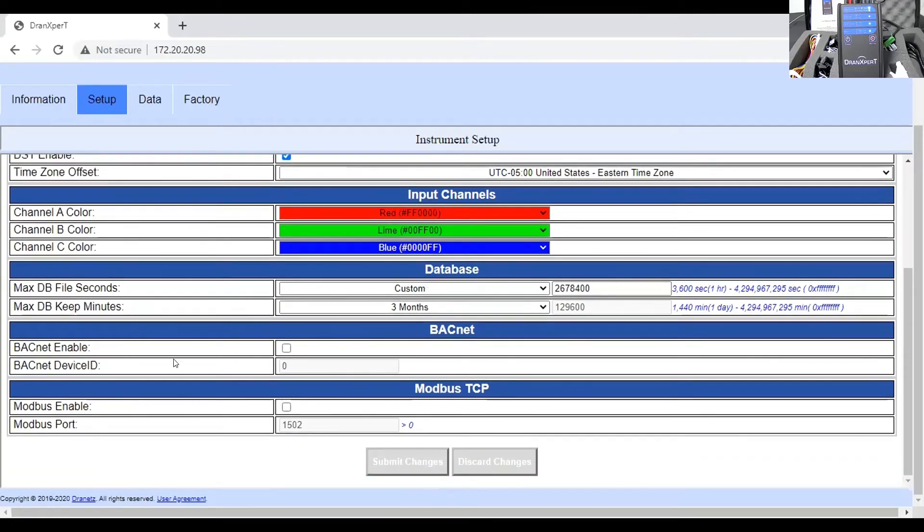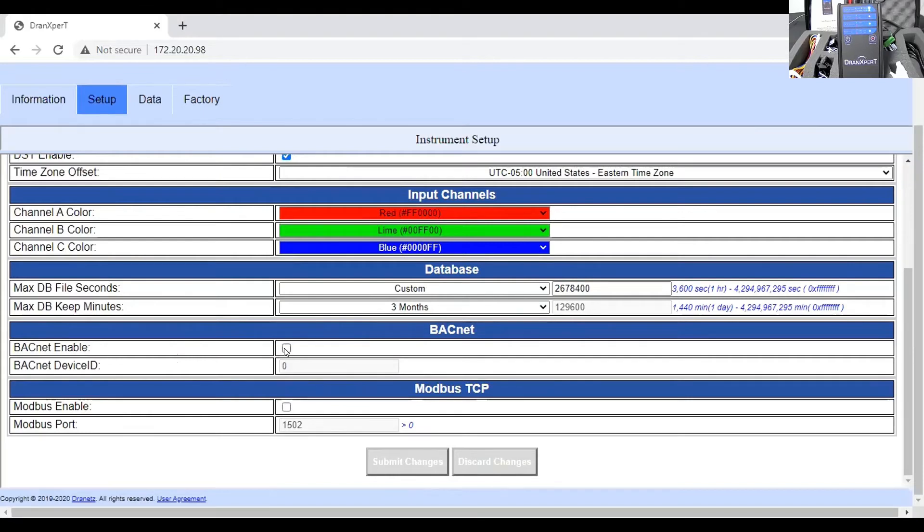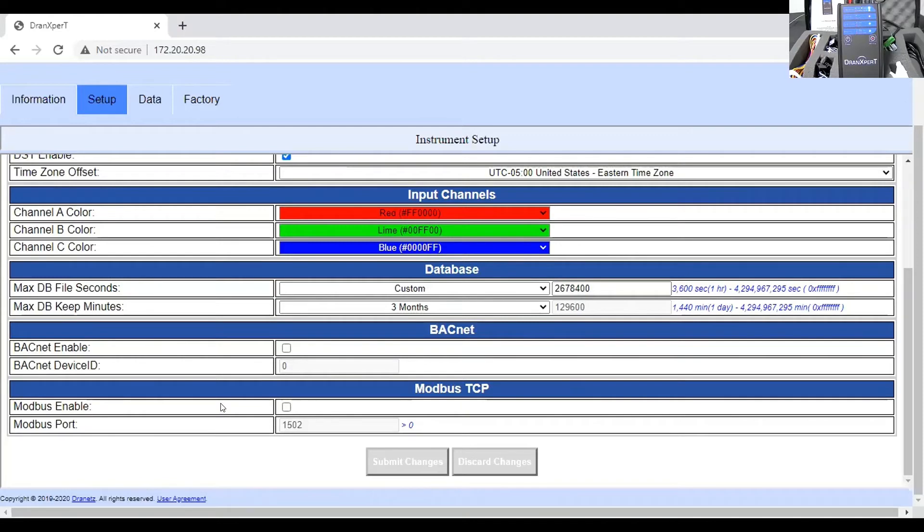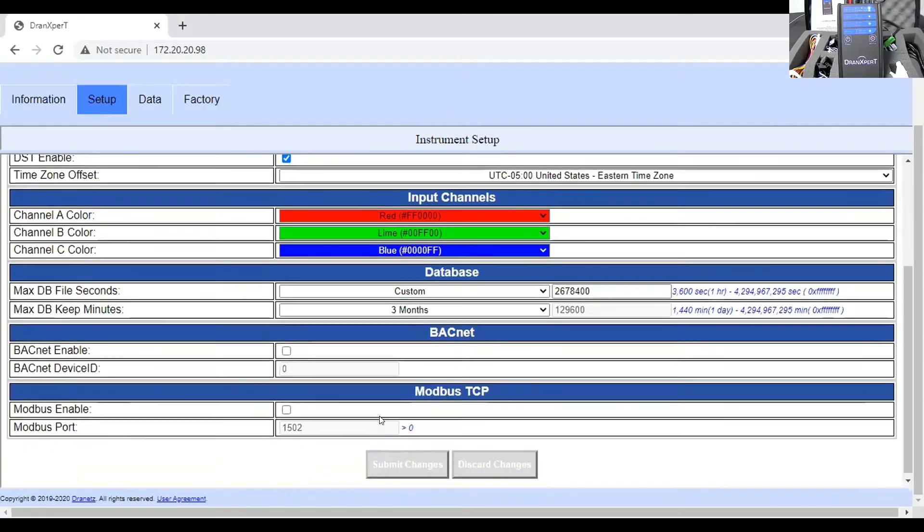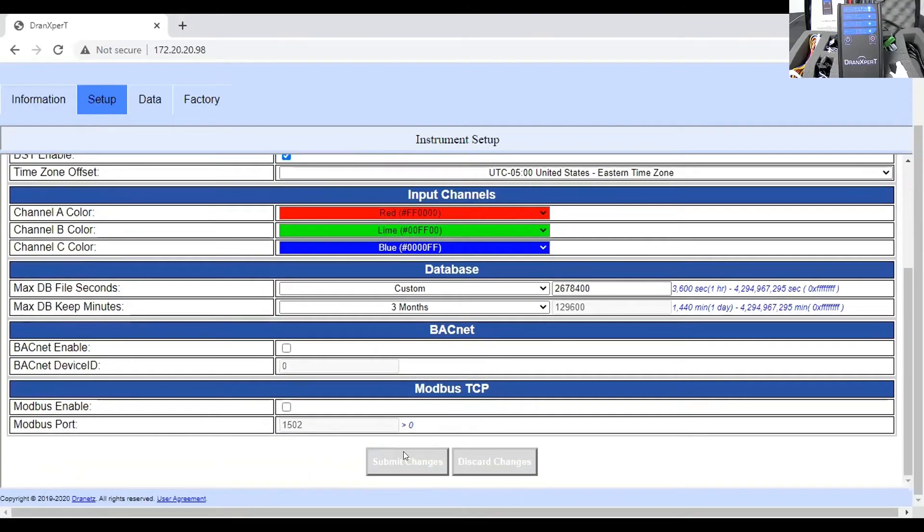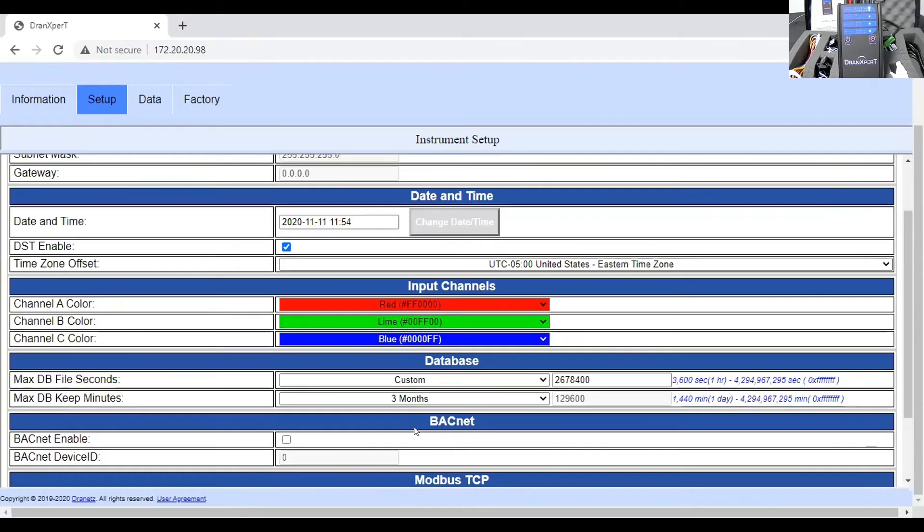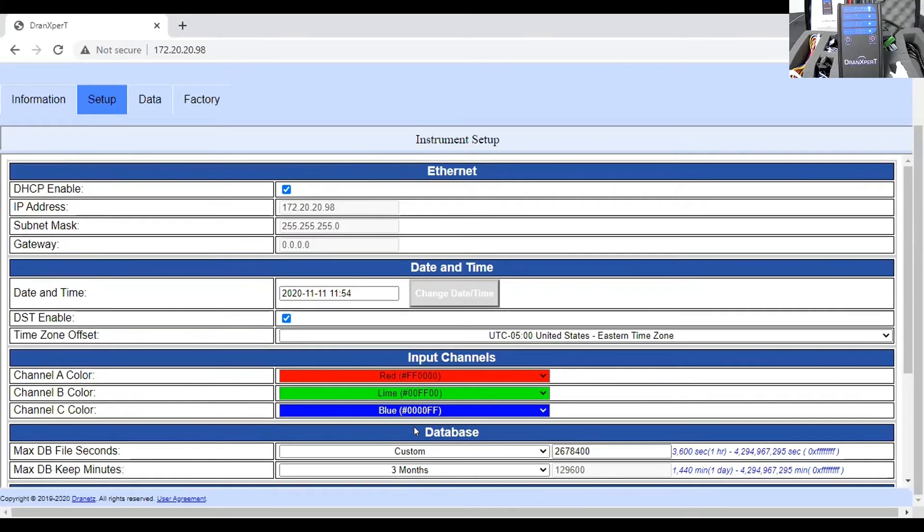So a quick review is these two lines mean how large of a data file do I collect. It can be one day, four hours. How long I keep the data file around before the instrument purges the file. The instrument has eight gigabytes of storage. So that is a lot of storage for a logger. So you have more than enough storage capacity. For those that might use the instrument as far as BACnet, using BACnet IP, here's where you would enter the information. Obviously, you enable it. And then you add what is called a device ID that's typically used in BACnet. But for those that are using the instrument as a Modbus slave, you simply enable it and you use the Modbus port. The standard Modbus port, by the way, is 502. And you would edit those values there. And then it's just a matter of just submitting the changes once you've edited the screen to your liking or for the application.